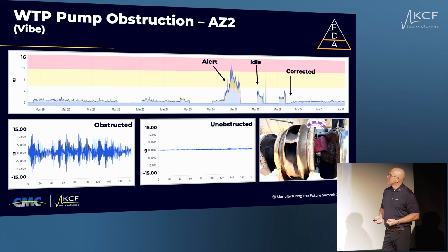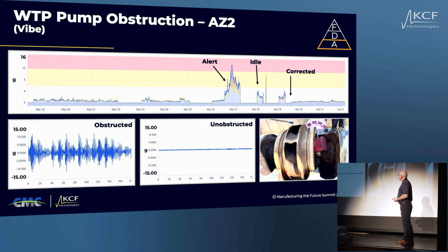Another abnormality, this one was in AZ2. This was on one of the water treatment plant pumps. You can see the alert there on March 27th, getting up into the alert band. We were able to idle the pump for a while until we were able to turn it off, split the coupling and investigate what the problem was. And you can't see it right there, but believe me, there's a plastic cap from a tube of welding rods. The plastic cap had gone through the water system and got stuck in the impeller, and that was causing the vibration. So that was a quick fix, pull the plastic cap out, and we went back to the unobstructed trend.